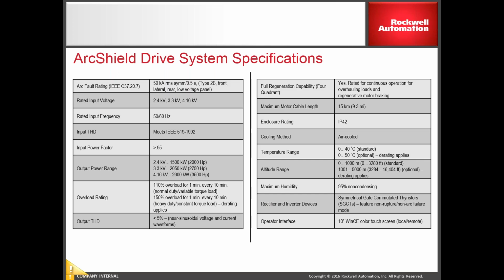It's just some system specifications. I'm not going to go through all of these, but again, the rated input voltage 2.4 kV up to 4160. We meet IEEE 519 with PowerFlex 7000. And I want to point out the cooling method. So this is air cooled only.